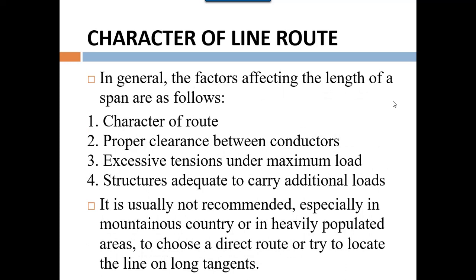In general, the factors affecting the length of a span are: one, character of the route; two, proper clearance between conductors; three, excessive tension under maximum load; four, structure adequate to carry additional load. These are the primary four factors to consider. It is usually not recommended, especially in mountain country or heavily populated areas, to choose a direct route or try to locate the line in a dangerous area.